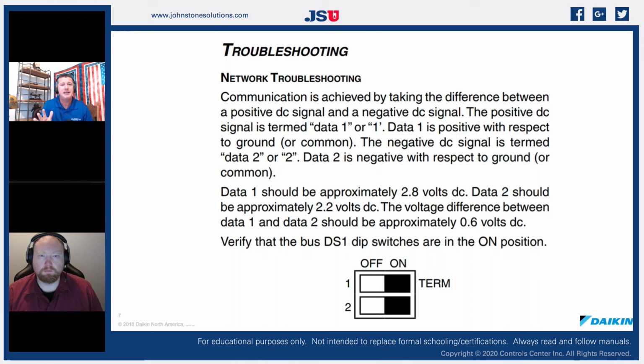So what they have provided is a bias balancing, and it's in the outdoor unit. On the outdoor unit, we have a switch called DS1. What DS1 will do is open up that bias so that we have a better bandwidth to communicate on. So if we do not have 0.6 volts, we can go to the outdoor unit, turn power off to the outdoor unit, flip the DS switches from off to on, and power that system back up, and hopefully our 0.6 volts has shown up.